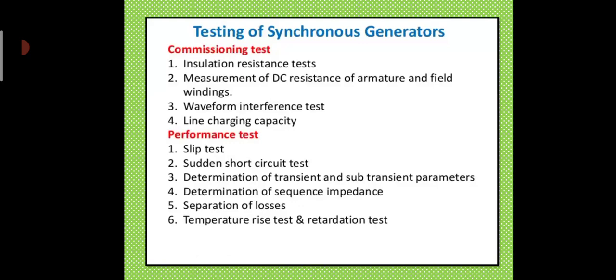Now, testing synchronous generators. In the commissioning test, first one is insulation resistance test, measurement of DC resistance of armature and field windings, waveform interference test, line charging capacity. In the performance test: slip test, open and short circuit test, determination of transient and subtransient parameters, determination of sequence impedance, separation of losses, temperature rise test and retardation test.